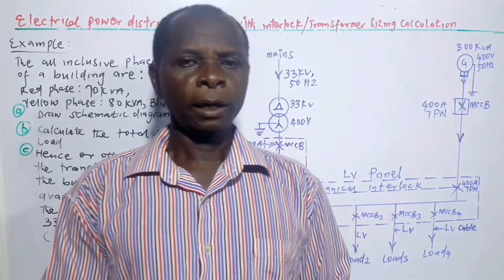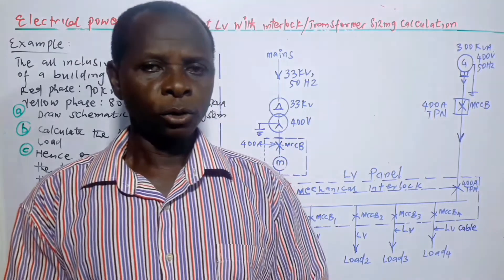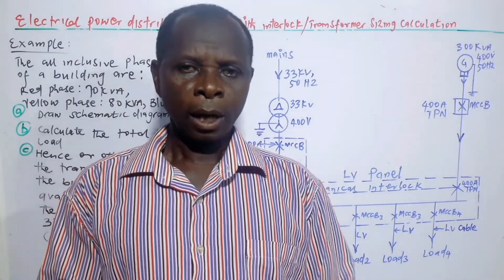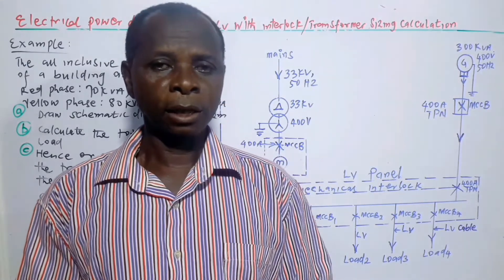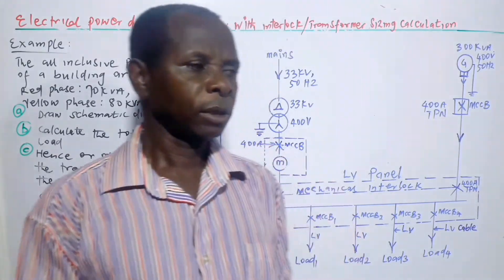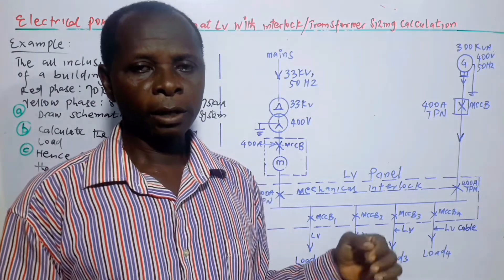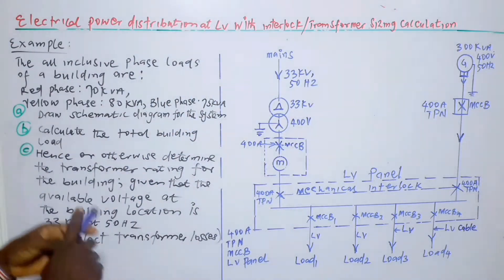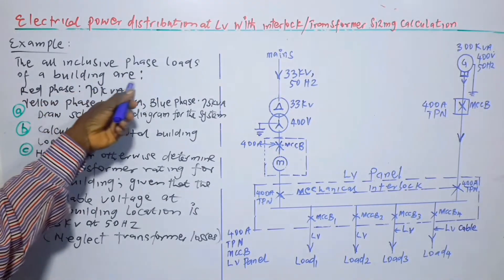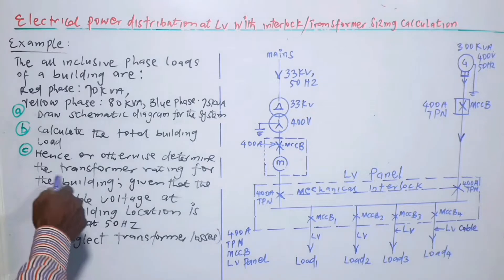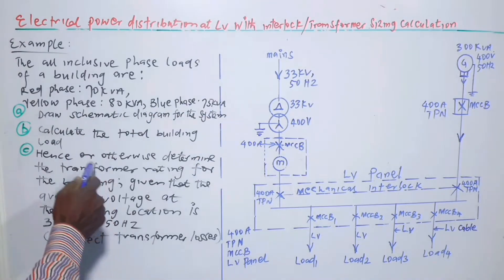For the purpose of a thorough understanding of the concept of a power distribution system at low voltage and transformer sizing calculation, the concept is illustrated making use of an example as follows. The all-inclusive phase loads of a building are: red phase 70 kVA, yellow phase 80 kVA, blue phase 75 kVA.